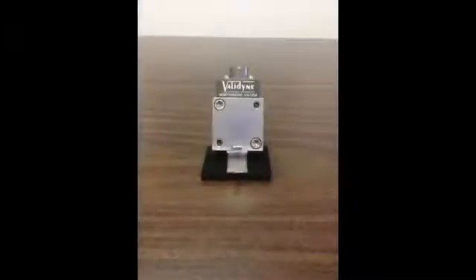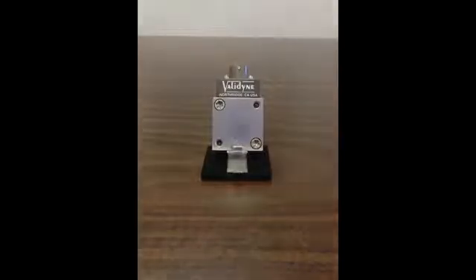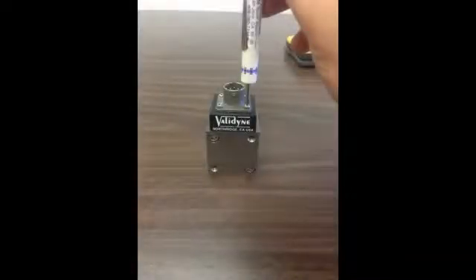Here is a typical DP-15 variable reluctance pressure sensor. The first test we will perform is a continuity check on the internal sensor coils. Loosen the two small screws holding the electrical connector and expose the wires underneath.